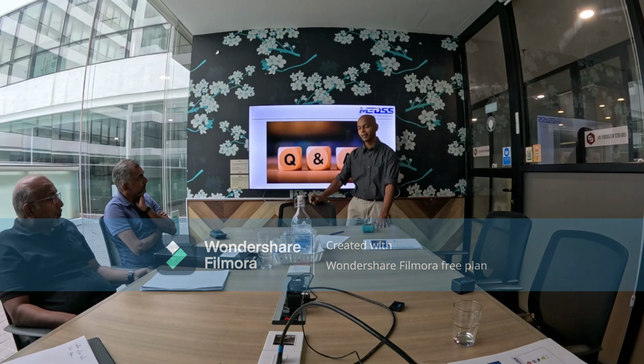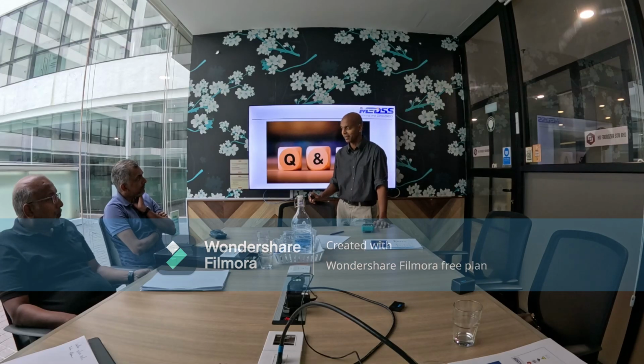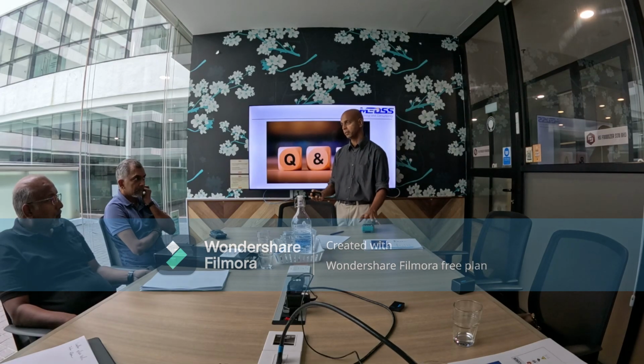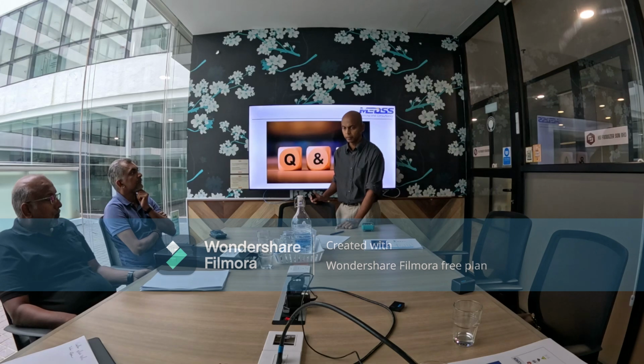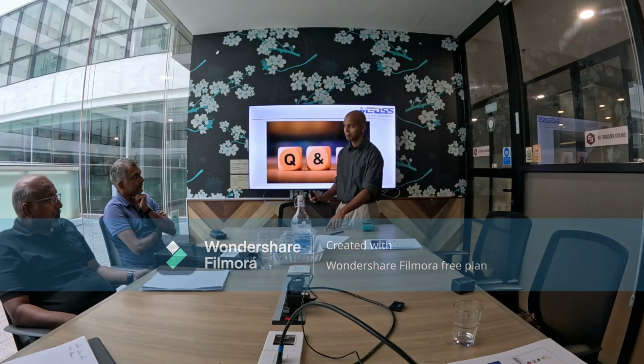One of the things I experienced was the IR tester - 1 kV or even 5 kV. There was one customer who came; it was already calibrated, ABB, all their equipment is calibrated on time. So at 1 kV, when we inject, it was showing about 800 something, 900 something. Then he asked why it's not injecting the correct amount as stated in the criteria.